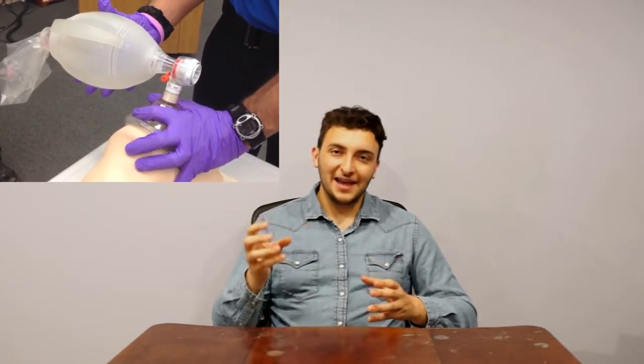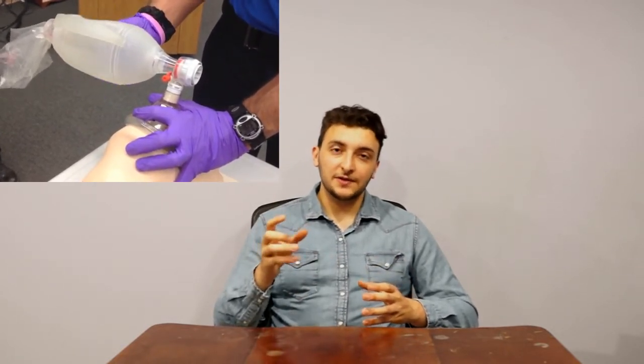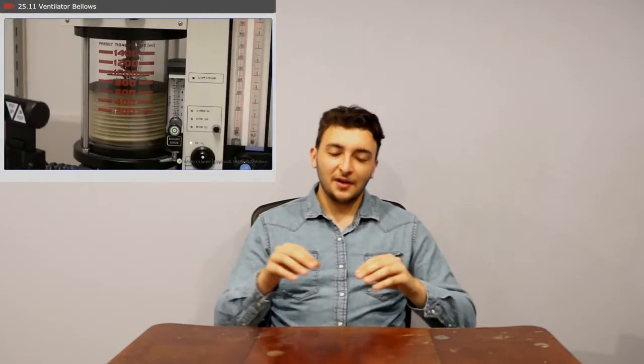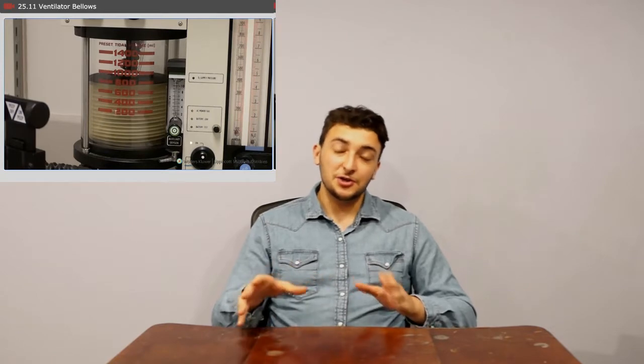They had a mechanical actuator to squeeze the device to deliver air to the patient instead of doing it by hand. The problem is that this only fulfills one of the functions that a real ventilator does, and it's incapable of handling the workload that a proper ventilator device can do. As such, it's only useful in very certain edge cases in the COVID pandemic, and they didn't see much utilization nationwide or even worldwide. Our device works on completely different principles.